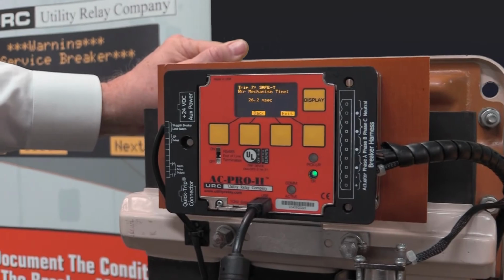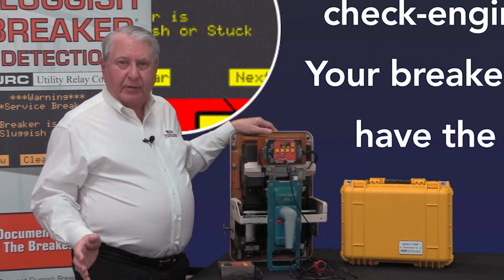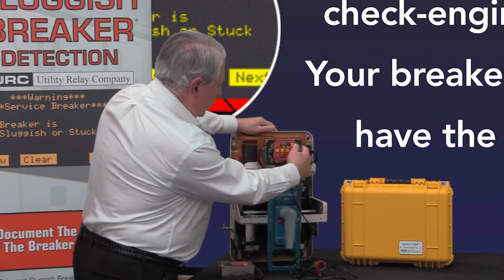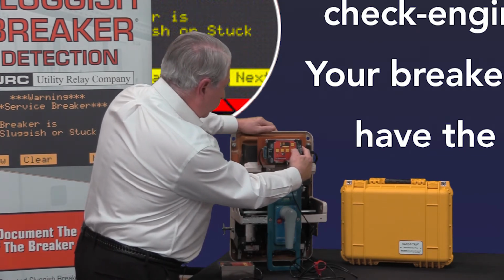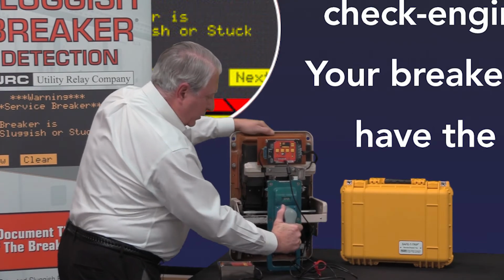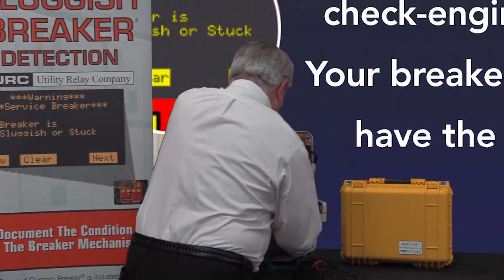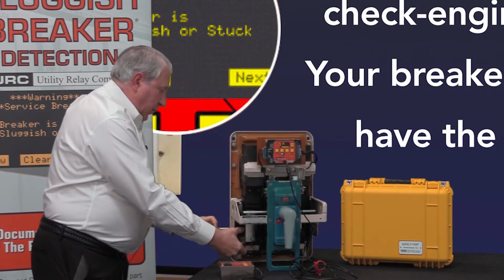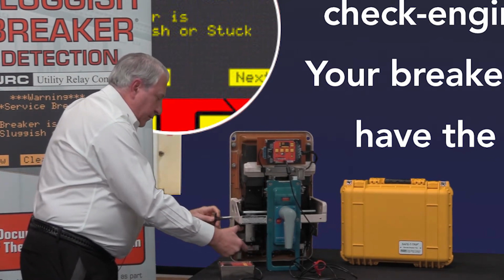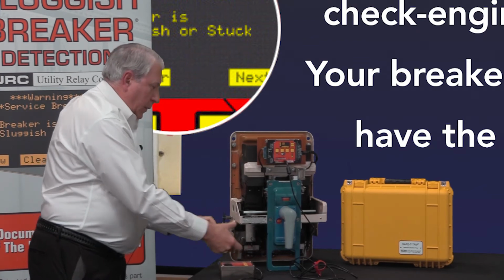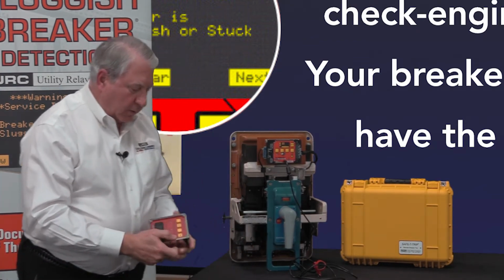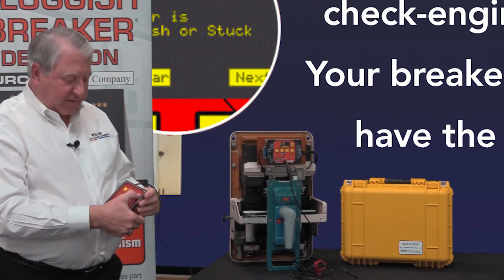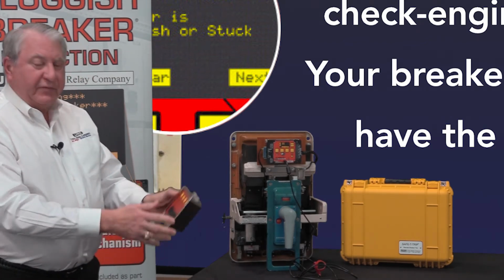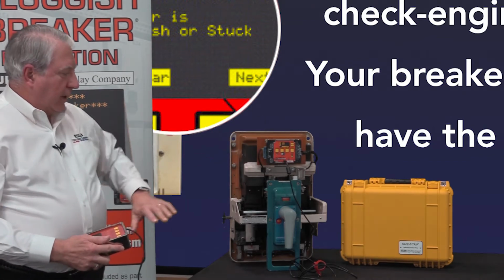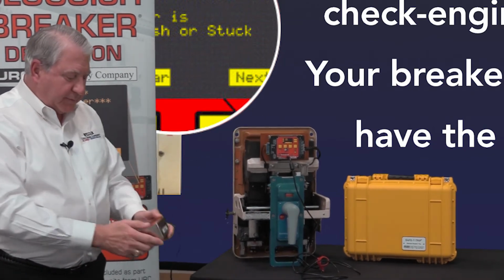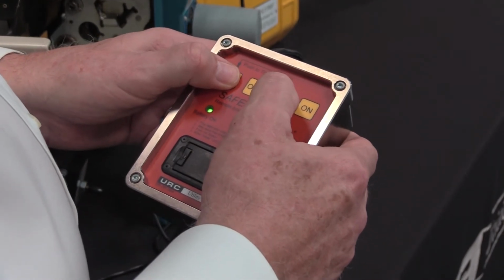So let me reset this and demonstrate a sluggish breaker opening. So I'm going to reset the entire setup. Have to reclose the breaker. To set it up for sluggish breaker now. And we will, again, activate the safety trip device. Wait for this to do its communication with the device. And now push the two buttons and it will.